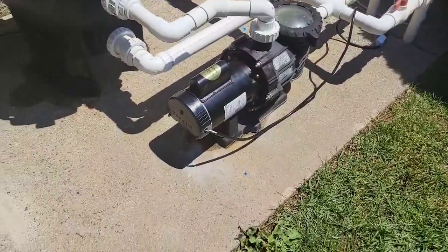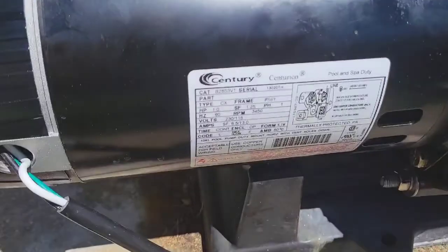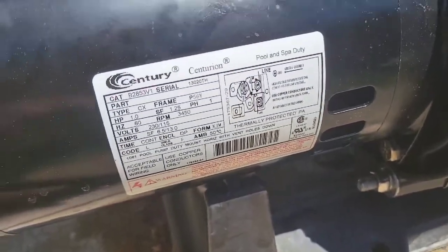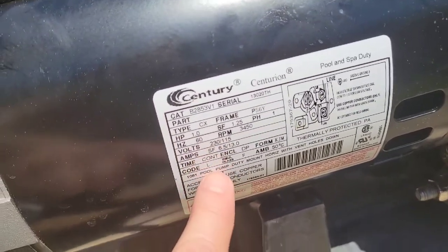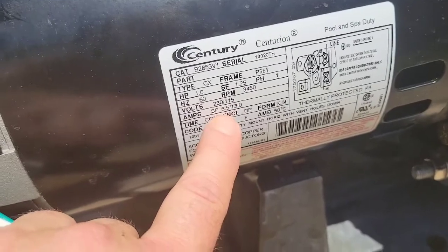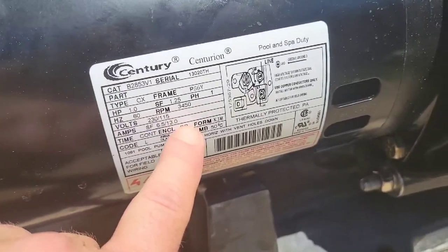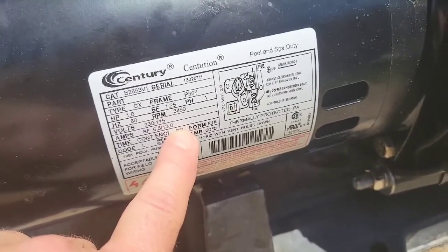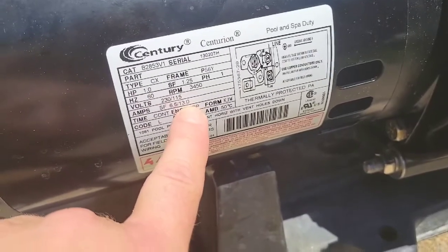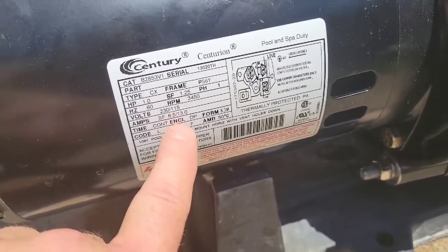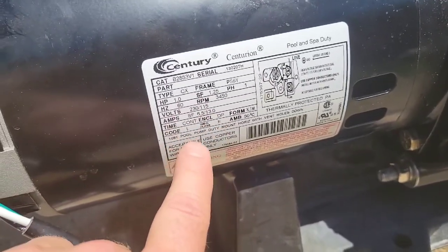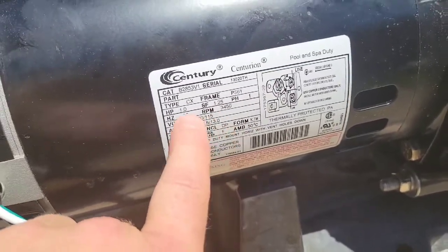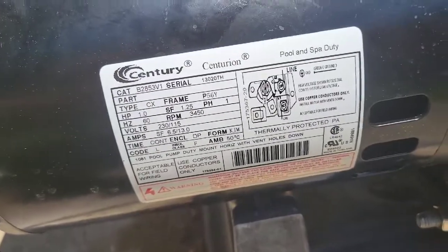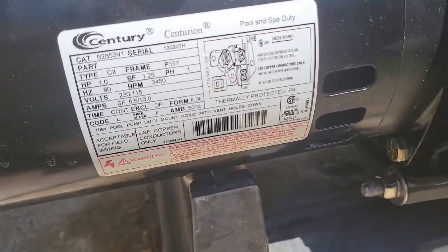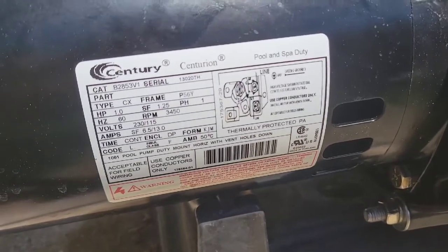So now I'm scratching my head, and I'm wondering, did I assume something wrong? Well, we looked at the label plate on the new motor, and you can see, I think, that it's rated for 230 or 115, and at 230 it draws 6.5 amps, and at 115 you double it because you're taking the voltage in half. It has 13 amps. So essentially what you have is a constant power motor. It's a 1 horsepower motor. So at 230 volts it draws 6.5 amps, and at 115 it draws 13 amps.